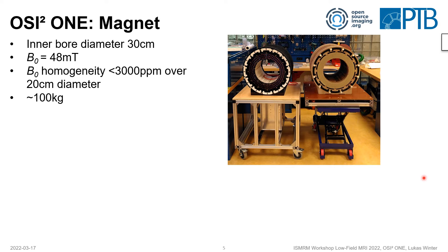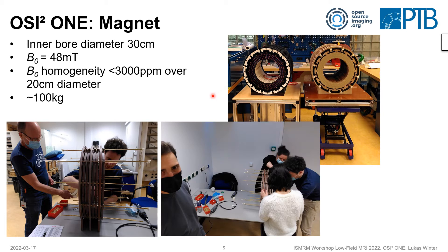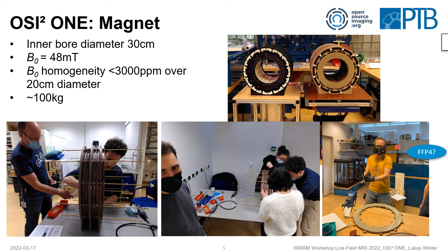Let's have a look at the system components of the low-field MRI scanner, starting with the magnet, which is the most challenging to reproduce. On the left side you can see the first build of this magnet, which was done in Leiden. Then we came over from Berlin to Leiden with our own components and slightly different materials to rebuild the system. The system consists of 25 rings with more than 4,000 12 mm cubic magnets. The rebuild was done by many people — many different hands, many possible systematic errors, etc.